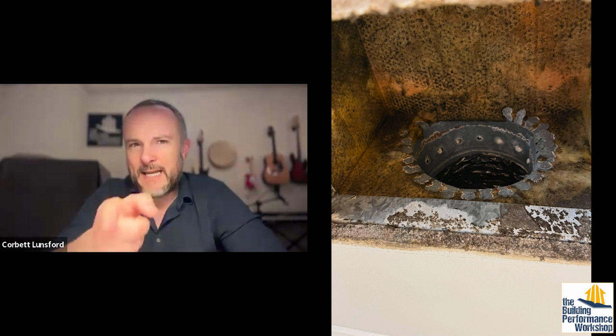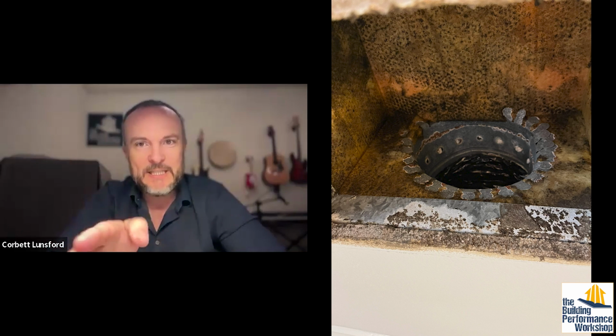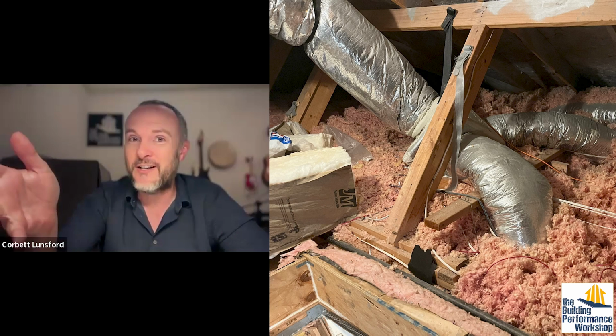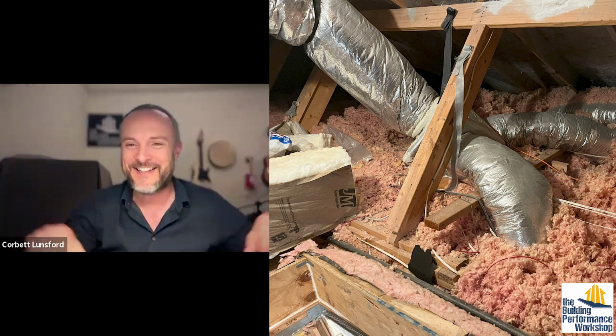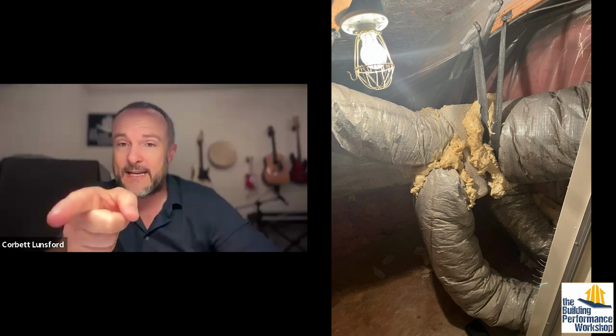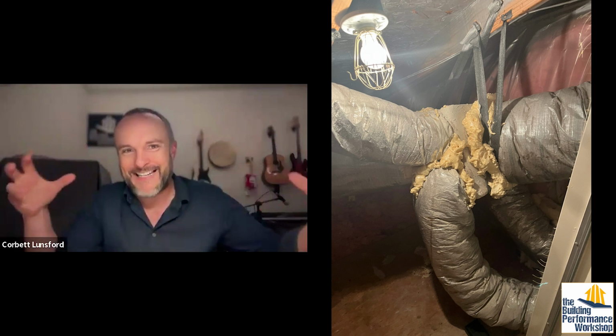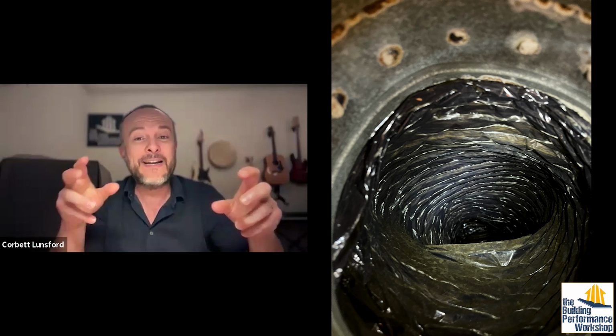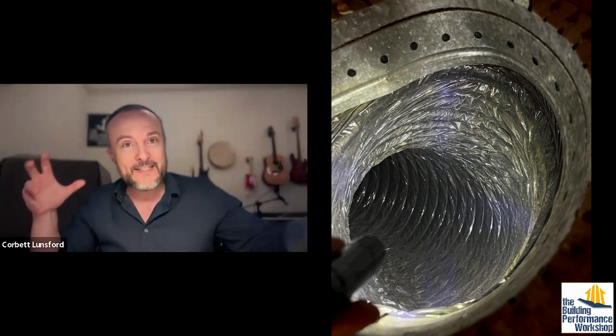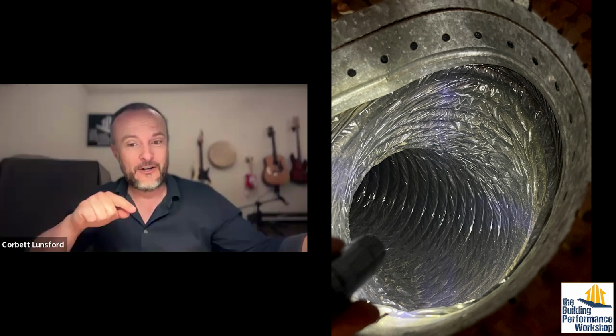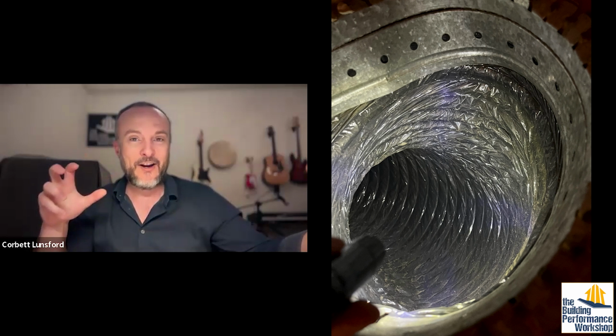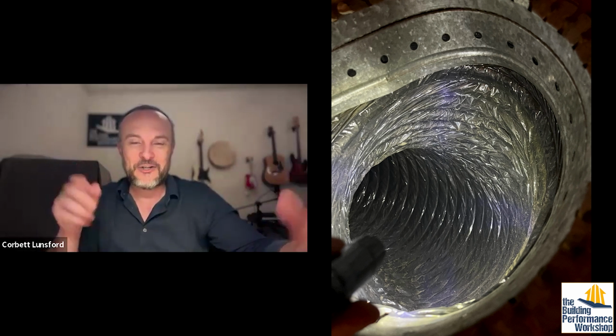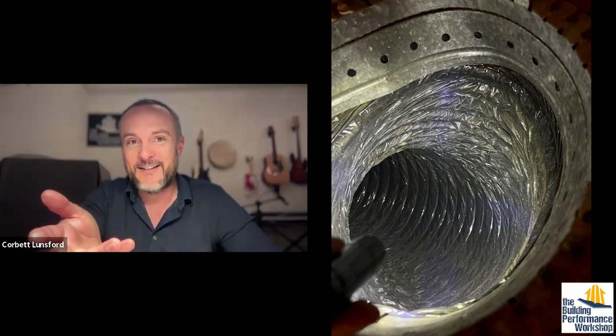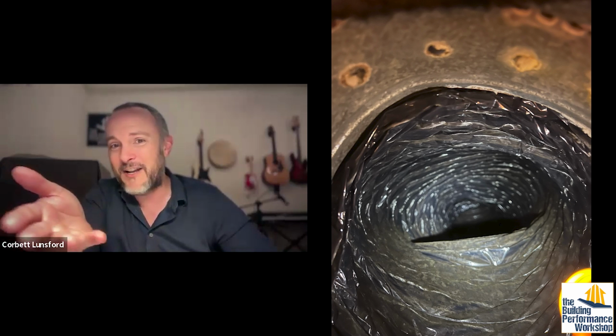It seems like with this kind of photo of flex duct specifically, which I would say is pretty universally enjoyed by HVAC professionals because it's very easy to install. You just stretch it out to length, you clasp it off, and it's very easy to install, but it's often installed poorly. The idea is to stretch it taut, which is actually hard. And if we want to be honest, a flex duct that is stretched as tight as we want it to be for airflow is more likely to degrade and tear because it doesn't have any give. So when ozone comes into the system and starts aging these materials, and this thing is like 30 years old, it's going to have little rips in it. If it's tight, then it's potentially pulling itself apart at that point.